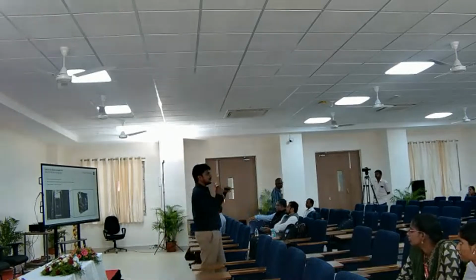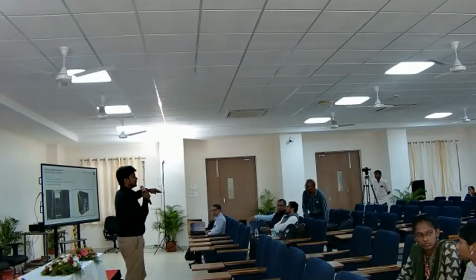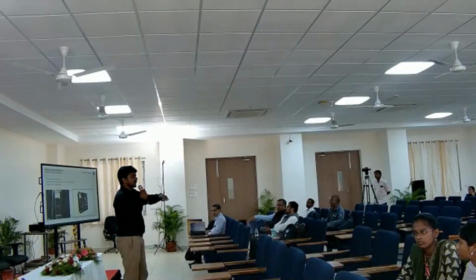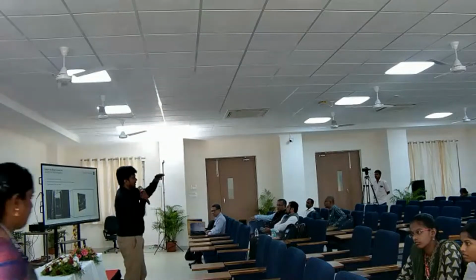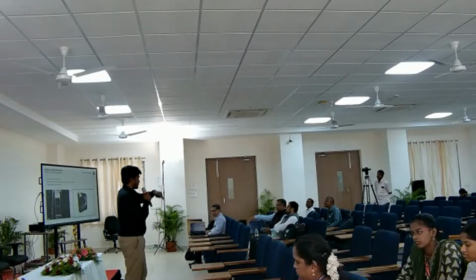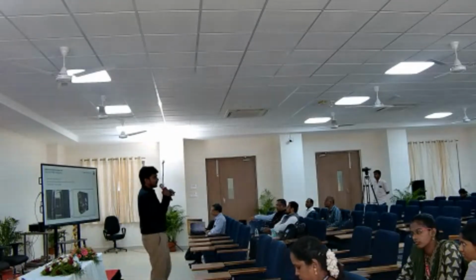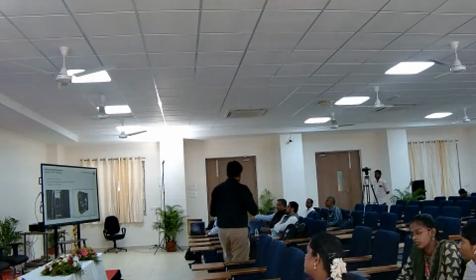Destructive is very simple. The ion beam is used for removing the material. Subsequently, the electron beam is used for capturing the image. So they go in serial. So removal of one layer, capturing the image. Remove the next layer, capture the image. You stack all these images one over the other, and you do a complete 3D volume rendering, and you get the three-dimensional data sets.